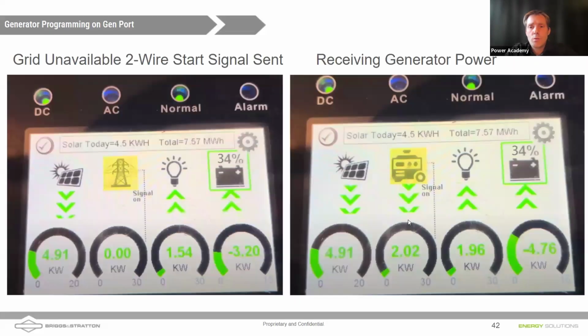So once the batteries get low enough to call for a generator to start up, the inverter is going to send a two-wire signal to start. Notice it only does this when the grid is down. The screen will display a yellow signal for grid here. This means that the grid has been disqualified, most likely because the grid's not there, but possibly because the grid is out of range. So if the grid has been disqualified, it will send a signal when the batteries get low to start up the generator. And once it starts up the generator, the grid icon will change into a generator icon, and you'll start to see the flow of power.